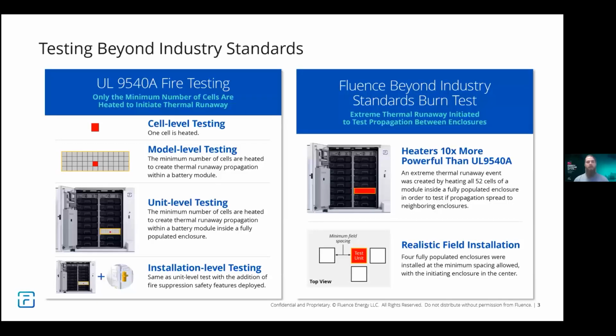Looking at the industry testing, 9540A is a testing methodology utilized throughout the industry that sets the standard so that every single player in the industry is testing the exact same way. That way, nobody's engineering a test to get particular results one way or another. This testing is conducted at the cell level, module level, unit level, and installation level.